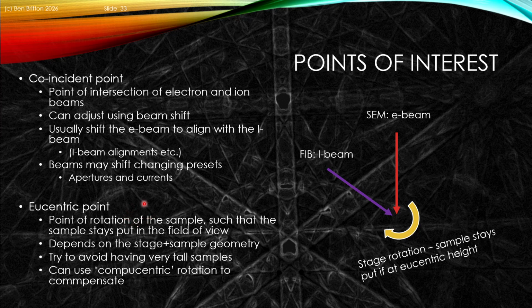This eucentric point, the second aspect, is how you tilt the sample to maintain it in the field of view. Traditionally, to help you in this, you want a sample to be not too high in the chamber. That just makes your life a bit easier if you can. This is set up so that, once the system is rotating the sample, the sample stays within the field of view.